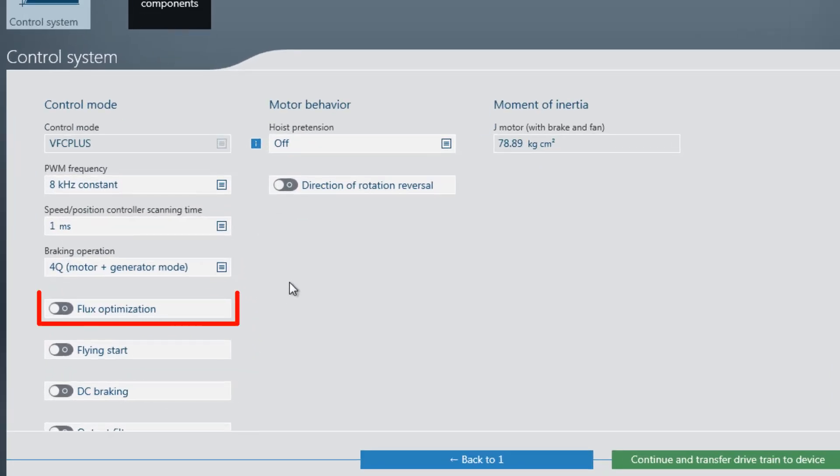The flux optimization is not allowed to be switched on when using an explosion-protected motor.